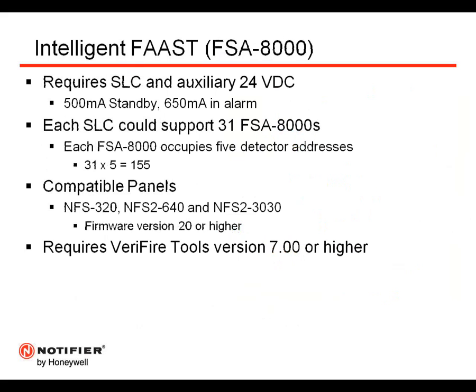Let's get into a little of the technical details of Intelligent FAAST FSA 8000 and FSA 8000A. Requires SLC. In addition to SLC, it does require auxiliary 24 volts power to provide the operating power for the Intelligent FAAST unit. Requires half an amp or 500 milliamps in standby, 650 milliamps in full alarm condition. And each SLC loop could support up to 31 FSA 8000 units. Each Intelligent FAAST unit occupies 5 detector addresses on an SLC loop. So at 5 addresses, with 31 FSA 8000s, takes up 155 points on that SLC loop.